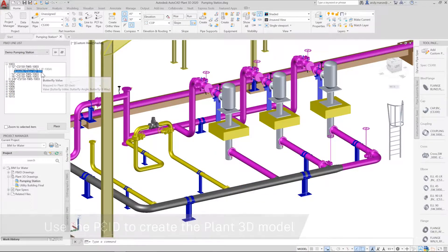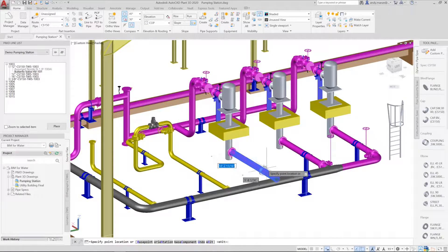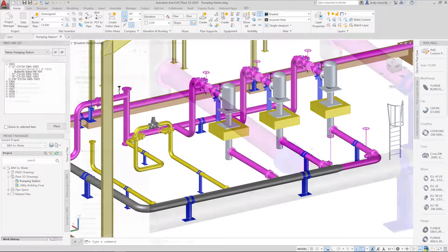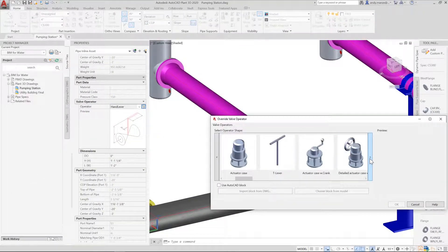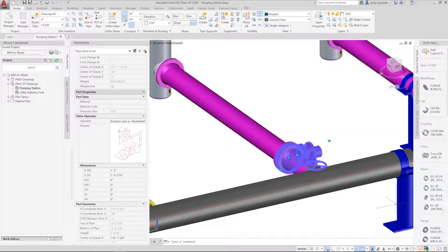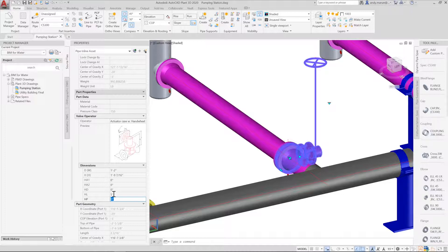The piping model is a 3D representation of the P&ID, and the data can be accessed while we are creating the piping. Lines and components are selected from the P&ID line list. Selecting the line transfers the P&ID data and also accesses the piping spec and catalogue to place the correct valve along with its mating flanges.